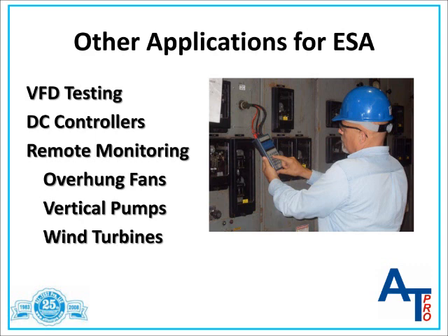Other areas of testing have also shown that since ESA uses the motor current as a transducer, ESA can identify problems in machines that have proven difficult, if not impossible, using MVA. One very promising area has been identifying pump problems in vertical pumps. It has been well documented that MVA cannot identify problems in the pump or other parts below the surface by making measurements at the only accessible locations on the motor or discharge stand. A recent test on a 750 horsepower condensate vertical pump in a co-generation plant clearly showed destructive vane passing issues using ESA. Vibration readings taken on the top of the pump showed the pump to be in excellent condition, but subsequent inspection revealed severe pump impeller damage.